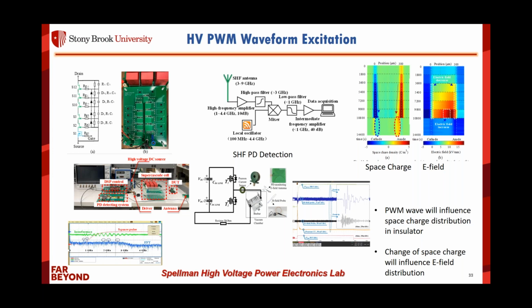So we combined this detection with some EMI research. Interestingly, we noticed that different insulators have different EMI signatures at different frequencies. Put simply, if you have a silicone or epoxy insulator, you'll see a high frequency unipolar signature at about 3 gigahertz. That 3 gigahertz discharge signal is relevant to the partial discharge event, and it's easy to separate from your EMI background noise.